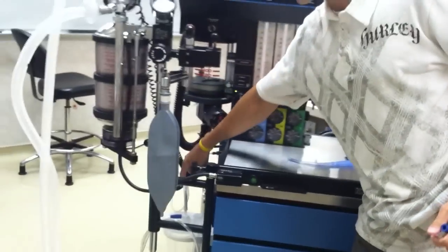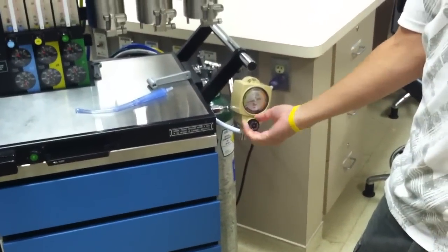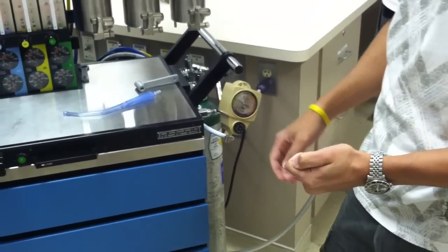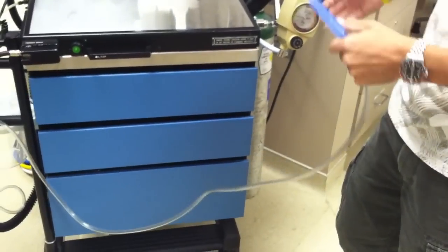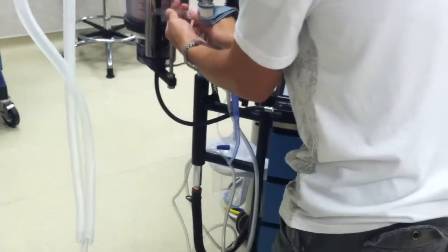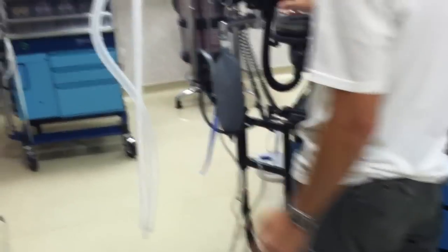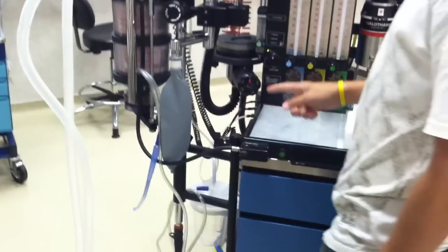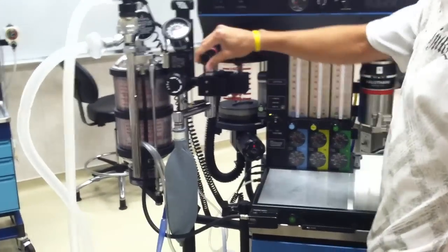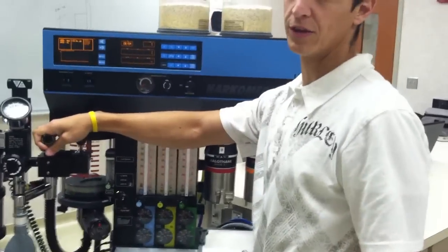Same on this machine, we need to make sure that the white hose is at the top of the canister, the suction canister. Then we can go ahead and make sure that we can regulate the suction, which we can. Put this back on. Make sure we always put it back to full. So before we leave, we want to make sure it's on bag mode. We want to make sure that our mask is on, and we want to make sure that the APL valve is completely open, which it is. And we are good to go, and that's how you do the machine checkout.